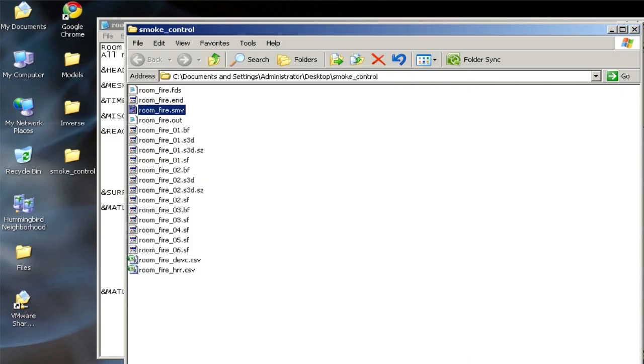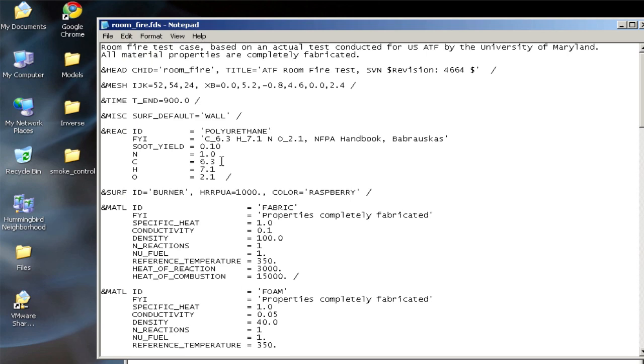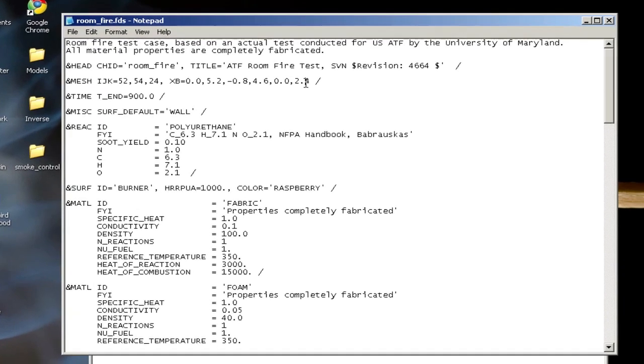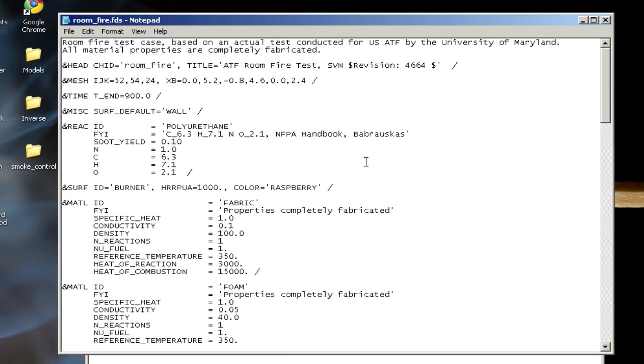And so if I go to the roomfire case, the first thing I want to do is extend the domain upwards, and I can do that on the mesh line. So first I'm going to change 2.4 to 2.8, and I should change the IJK line to match. So instead of 24, I'll make it 28. So now I've extended 0.4 meters in the Z positive direction.